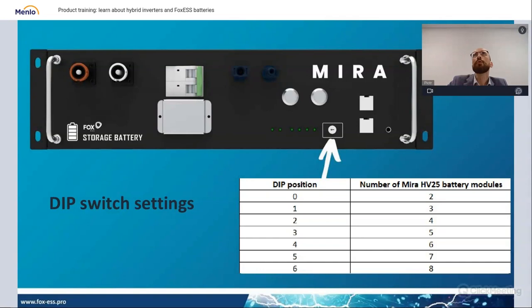This is really important to set, because if we have a different amount of batteries than we selected on the dip switch, the BMS will not provide power to the inverter. It will power up, go into fault mode, and start beeping. So it's important to set, and it's really simple, because this setting is the amount of batteries connected to the system minus 2, and you will get your dip position this way. After selecting the proper position, the BMS will start, and this green LED will go fully lit.